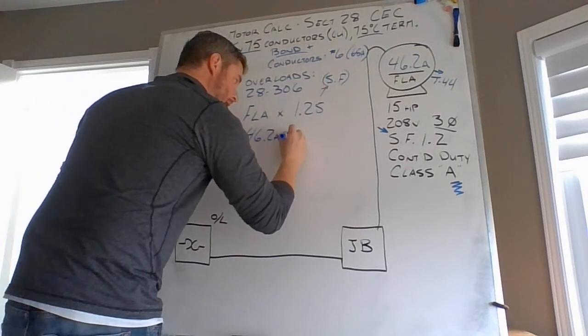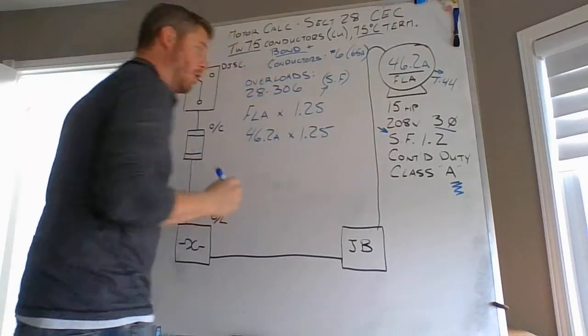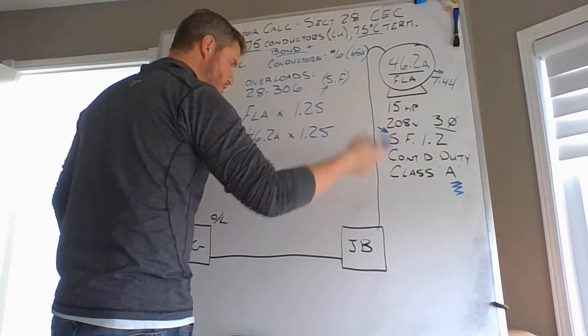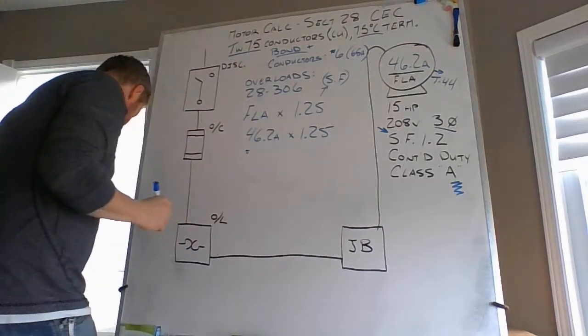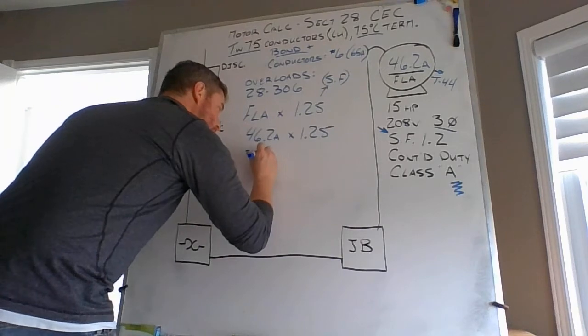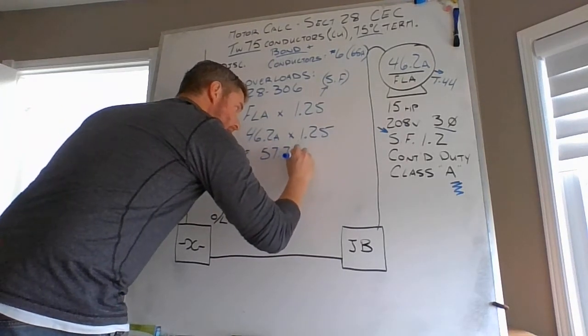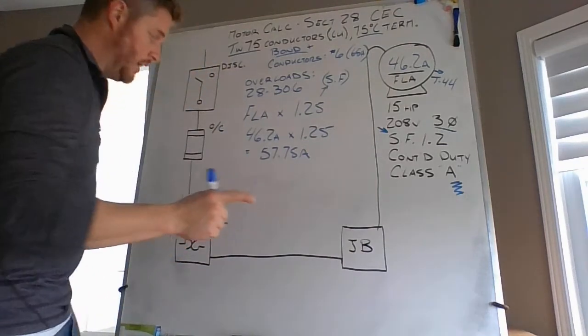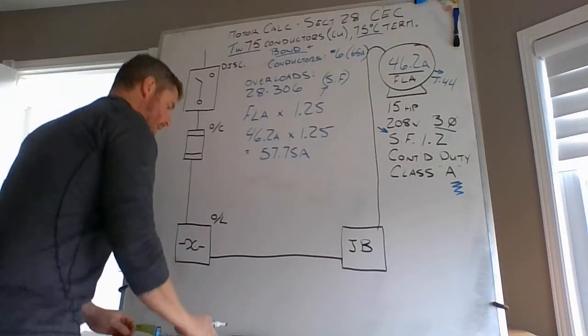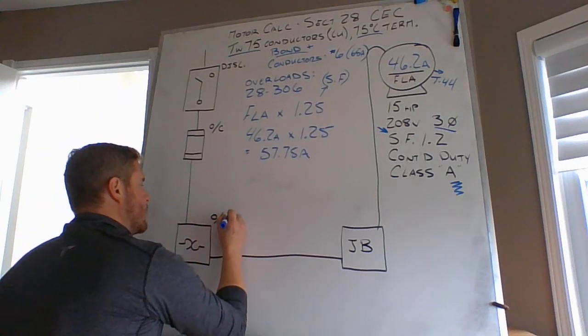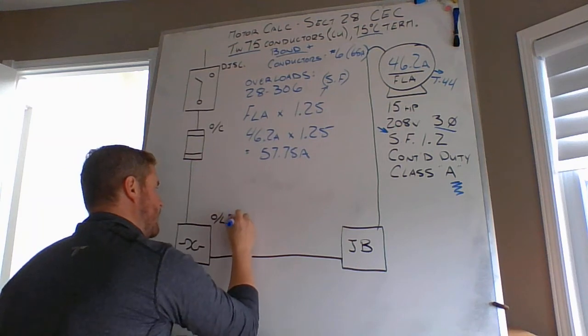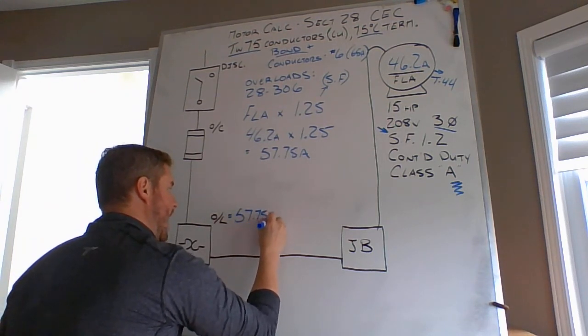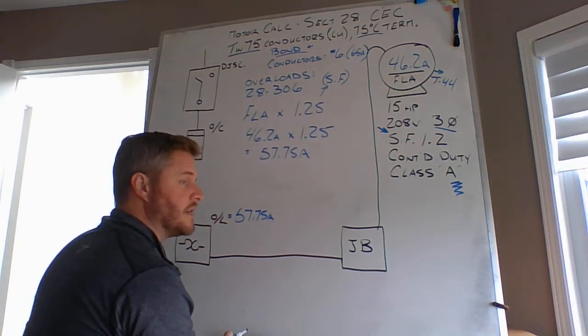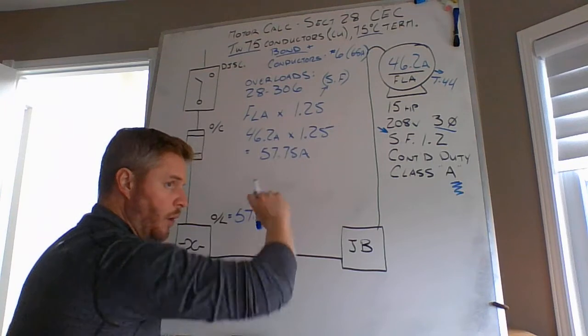46.2 amps multiplied by 1.25 as a multiplier, because your service factor is 1.2. Your 1.25 is your multiplier. In that case, you come up to relatively exactly the same number, being 57.75 amps. And this is going to be the rating or the setting of your overload component down here. So now your overloads are going to be set to 57.75 amps. Just like on the IEC starter, you'll see that there's a dial to set your overload component to.